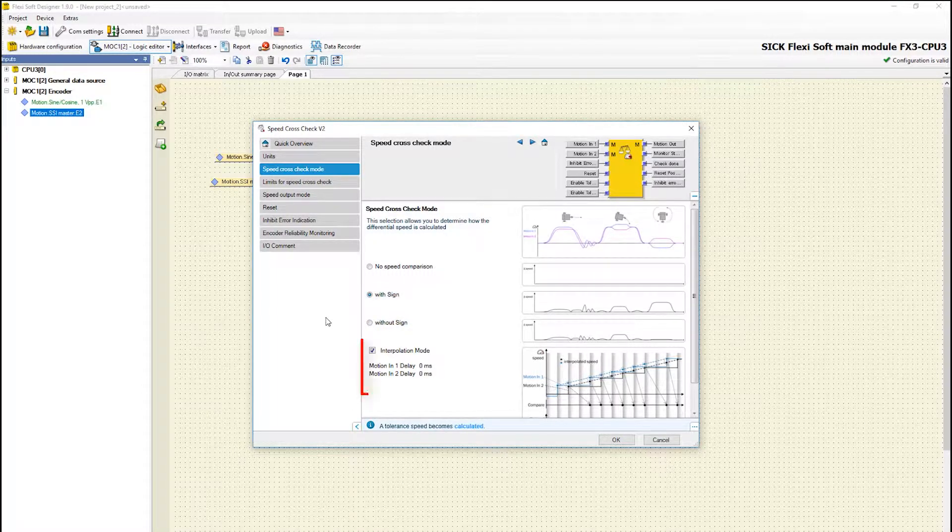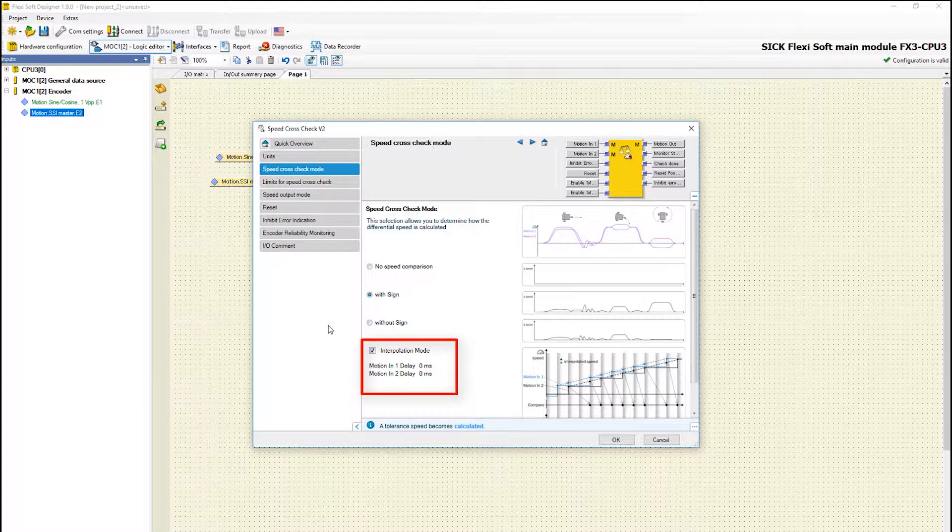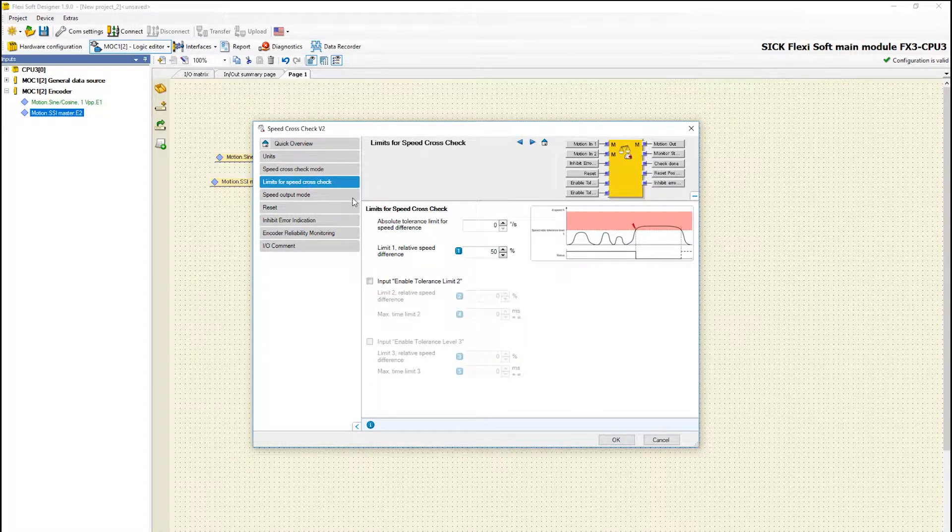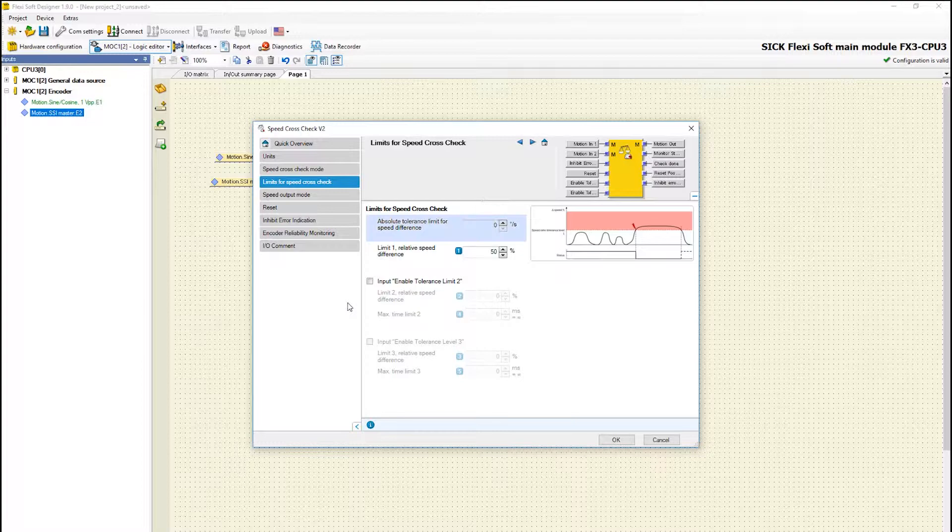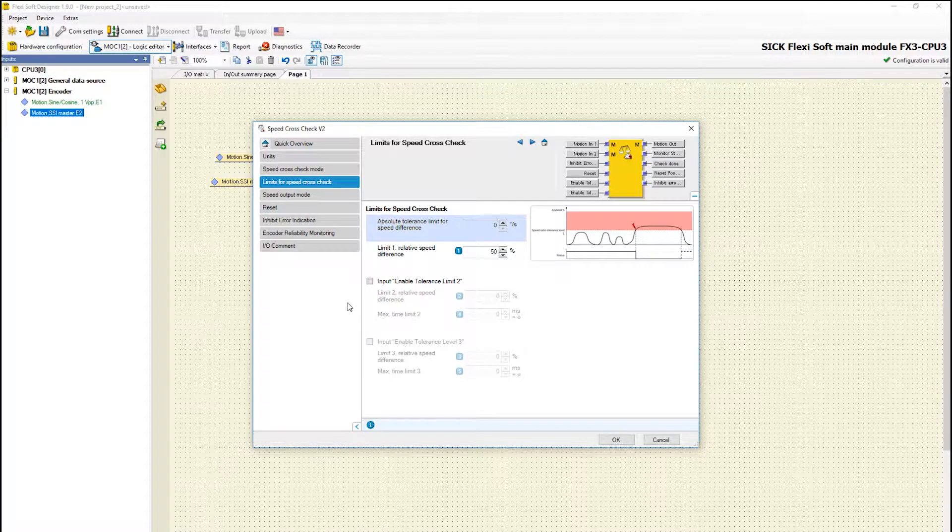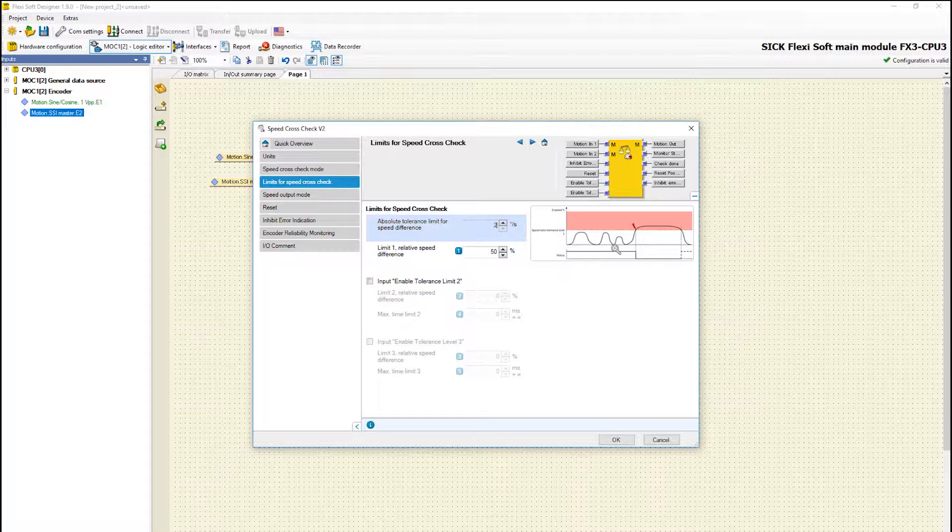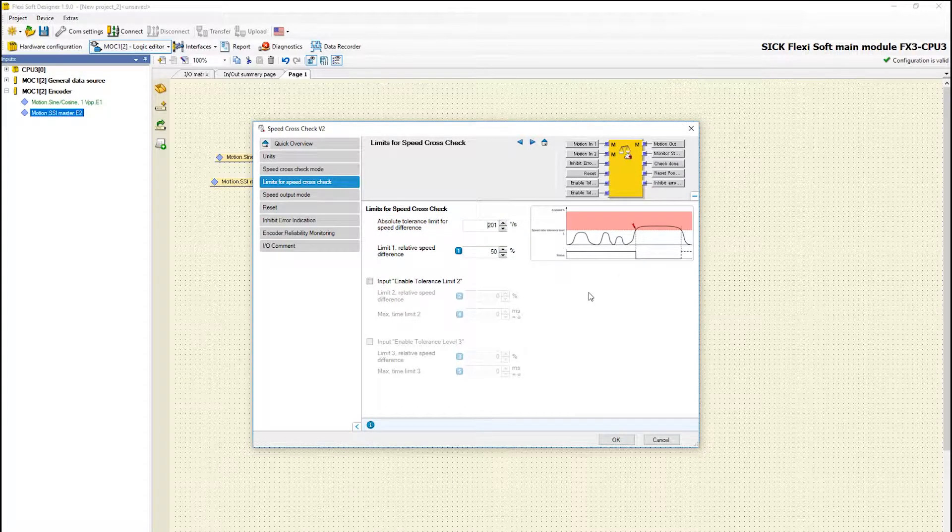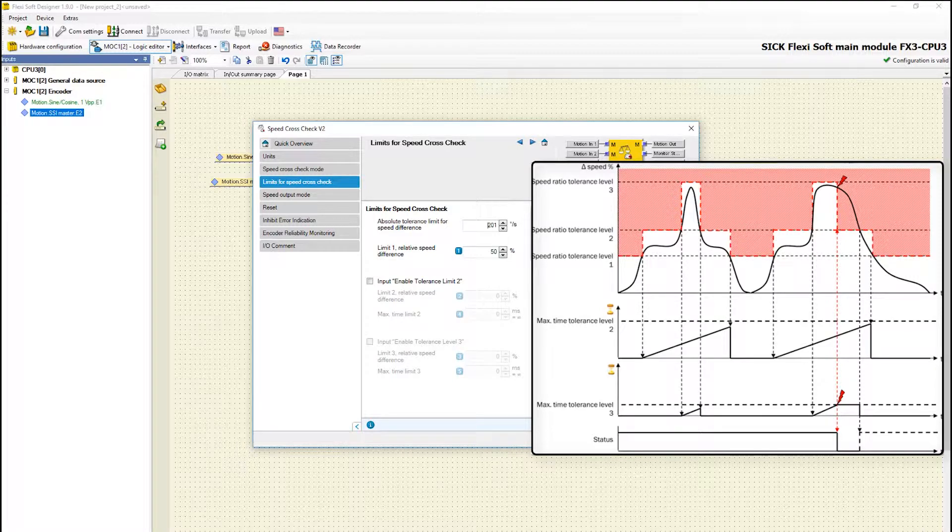The function interpolation mode is not relevant for this tutorial. In the next tab speed cross check limits the tolerance limits for the speed cross check are defined. With the parameter speed difference tolerance level the absolute permissible difference of the speed values from motion in 1 and motion in 2 can be defined. The permissible relative speed difference can be set with the parameter speed ratio tolerance levels.